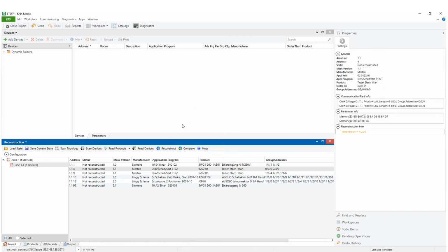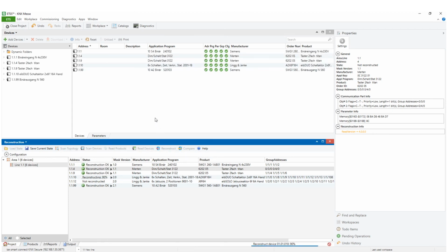The next step is to reconstruct. Up to now, no devices are shown here. Now we reconstruct. With this step, the right parameter settings are calculated, the device will be placed into the ETS project, and the group objects are linked with the group addresses. Now you see all the devices and they are set at Reconstruction OK in the Reconstruction app.